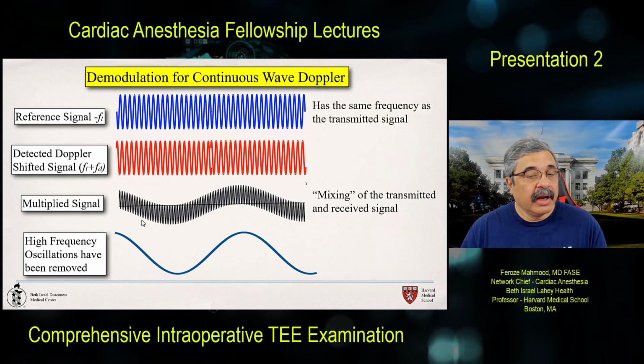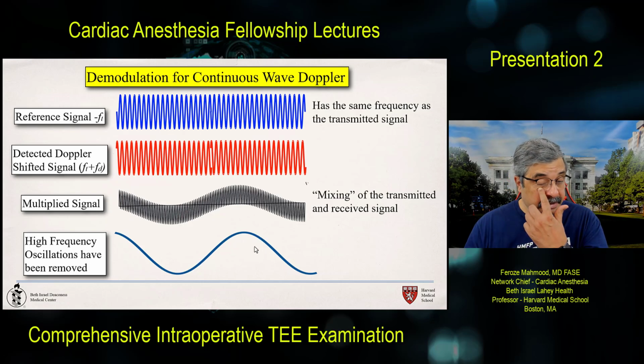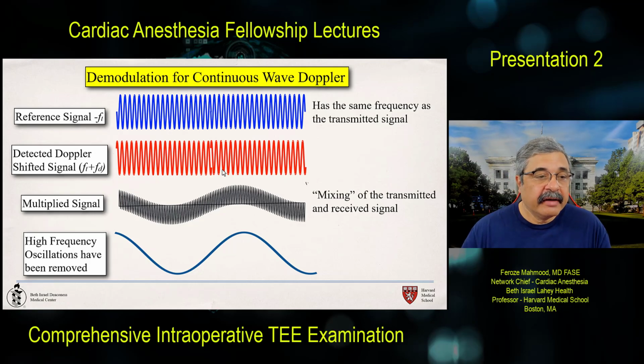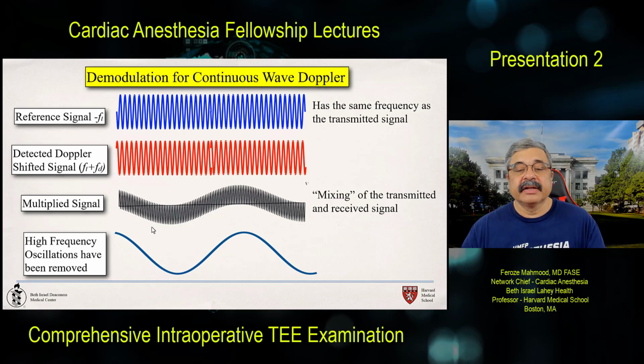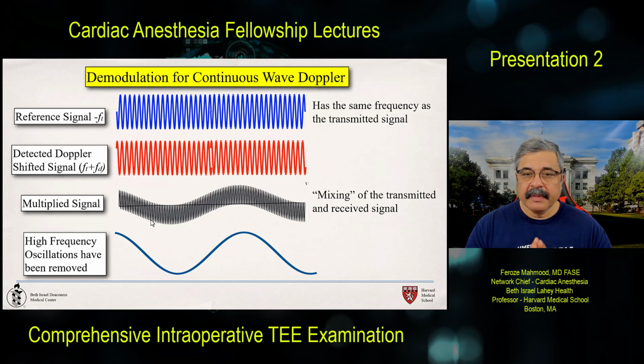And later on, high frequency oscillations during the process of demodulation are removed, and what is left is the level of out of syncness with each other, out of synchronization with each other, and that is referred to as Doppler shift, which means you have a reference signal, you have the detected signal. Both of them are mixed, and you find out by multiplying them where they are out of sync with each other. They're mixed and multiplied, and high frequency oscillations are removed, and what remains is a continuous wave Doppler signal.